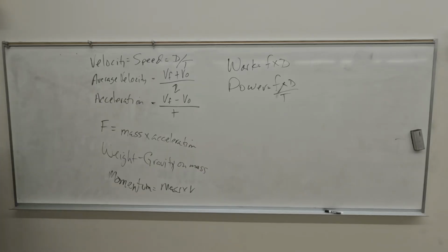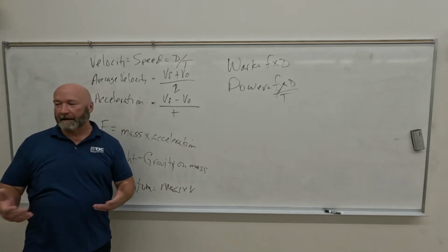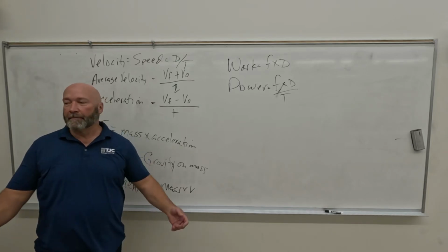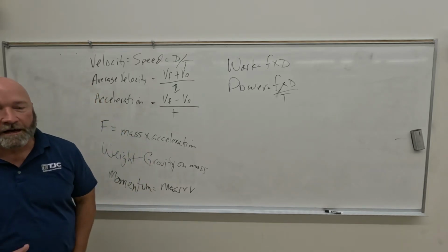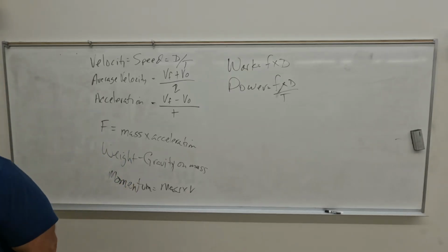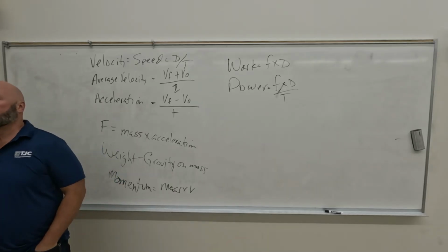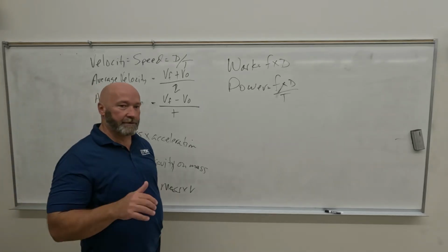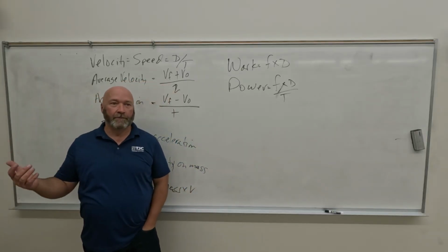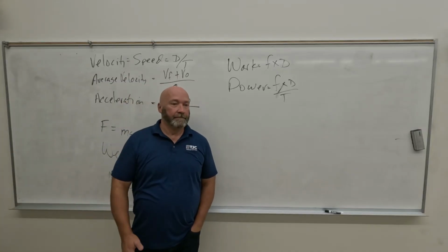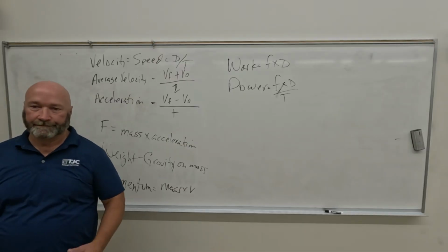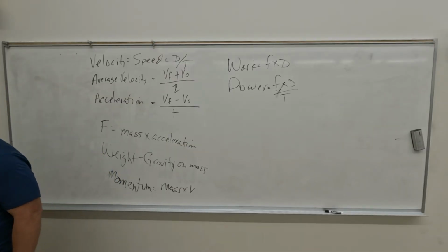Again, if you've got the Bushong workbook, he probably has math problems in there you can work out for all of that. I'm not going to make you work any of those out. Where does the power apply, like in the tube? Oh, good question. In the X-ray tube itself, it doesn't, but our machines are going to have a power rating. Like our machine upstairs may be a 25 kilowatt X-ray machine, okay? So in the tube though, we just break down to kVp and mA.